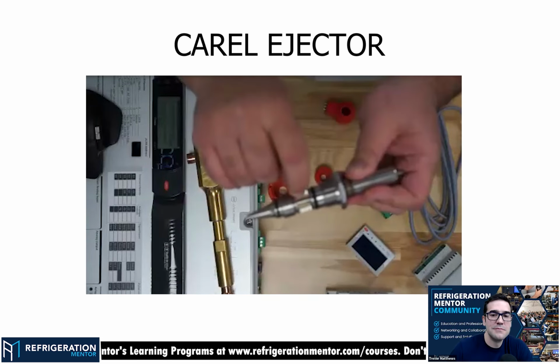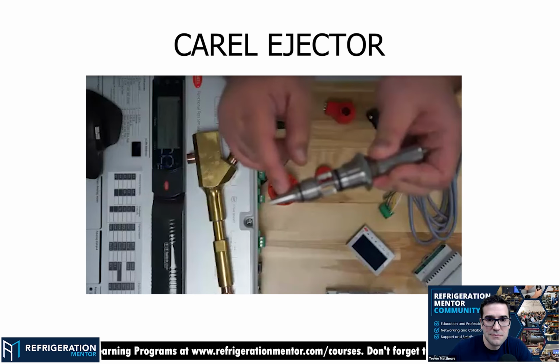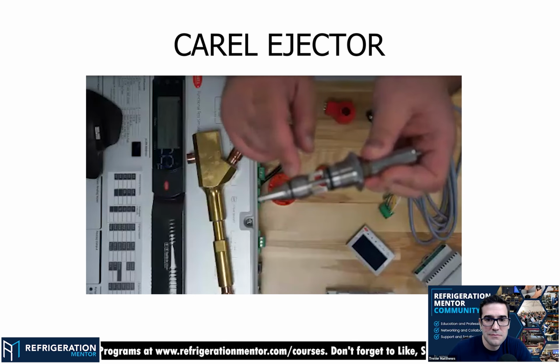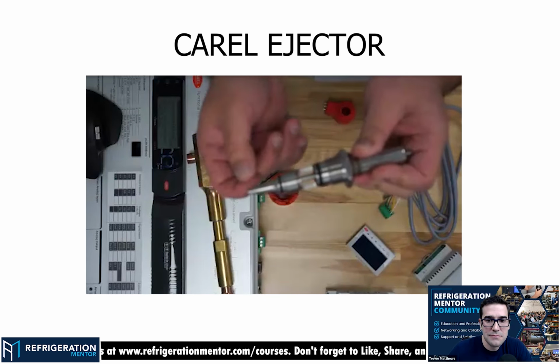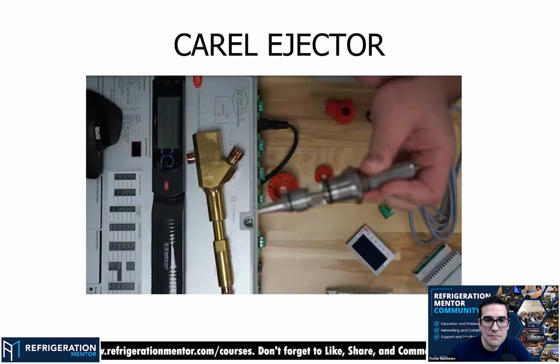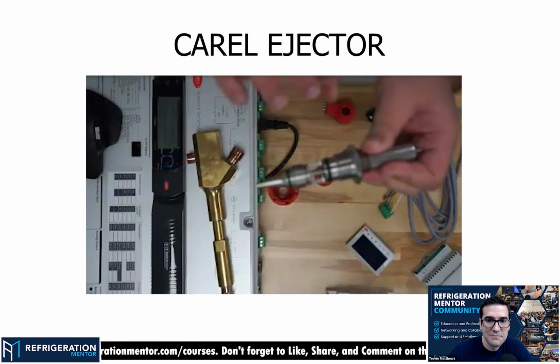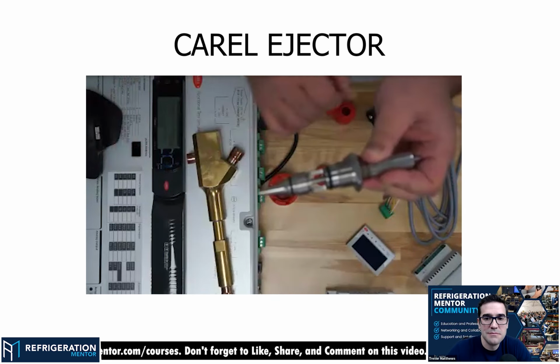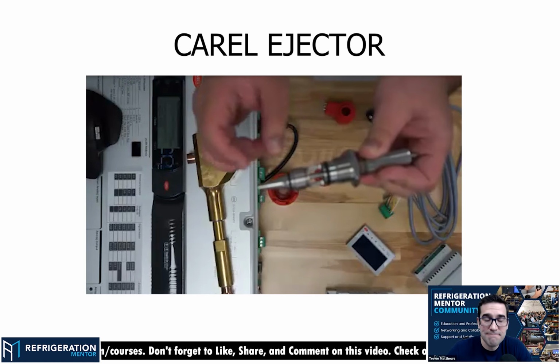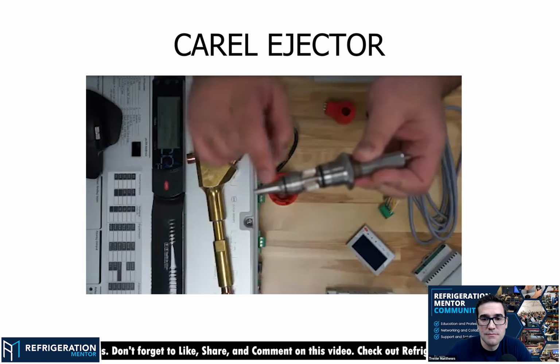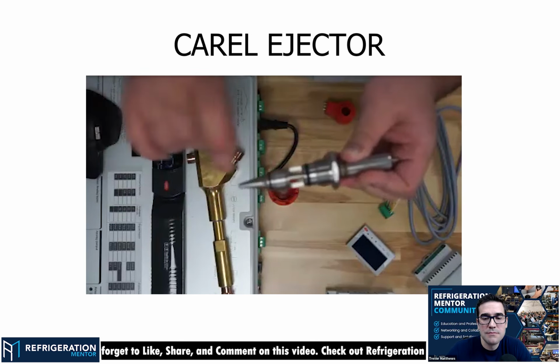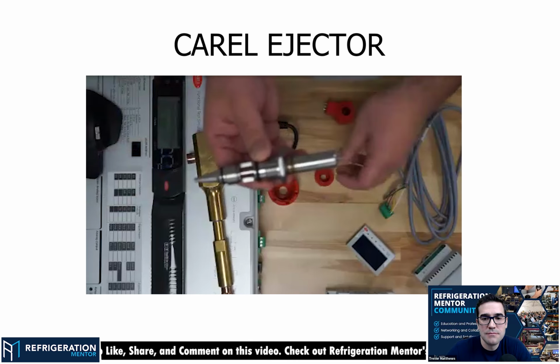And here you can see that I have the needle, and the needle is controlling the amount of refrigerant flow that can pass through the ejector. So this needle can go up and down and make sure that we have the precise refrigerant flow that we need for that specific application. And this is what it is controlling. And the ejector will take effect from this part, from the suction line.